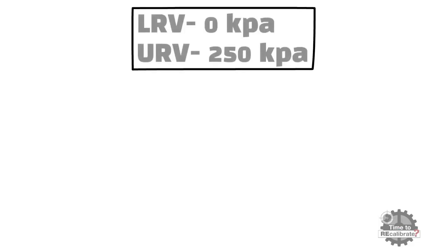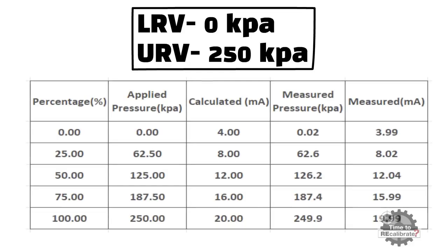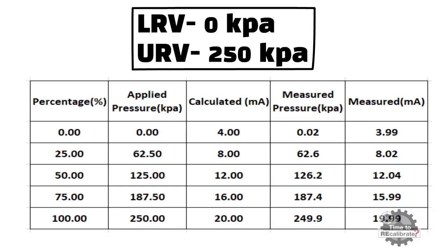Now, you should have the lower range value and upper range value in order to perform a 5-point verification test. You can also get these values by connecting a HART instrument in series with pressure transmitter. In this example, the lower range value is 0 kPa, and the upper range value is 250 kPa. Now, divide 250 into 4 equal parts. For example, 25% of 250 is 62.50. So, put this value in the applied pressure column just beside 25%. Calculate the same value for 50% and 75% of 250 and put these values in the applied pressure column.